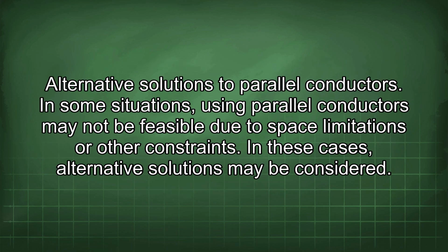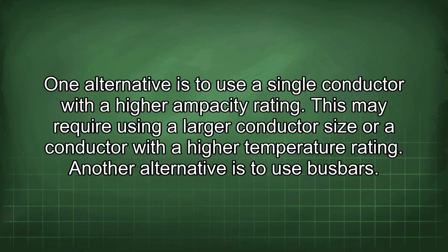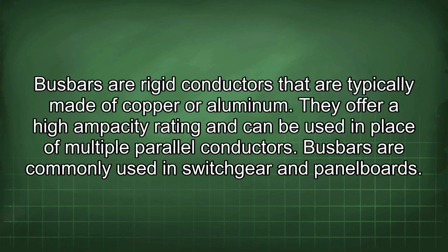Alternative solutions to parallel conductors. In some situations, using parallel conductors may not be feasible due to space limitations or other constraints. In these cases, alternative solutions may be considered. One alternative is to use a single conductor with a higher ampacity rating. This may require using a larger conductor size or a conductor with a higher temperature rating. Another alternative is to use busbars. Busbars are rigid conductors that are typically made of copper or aluminum. They offer a high ampacity rating and can be used in place of multiple parallel conductors. Busbars are commonly used in switchgear and panel boards.